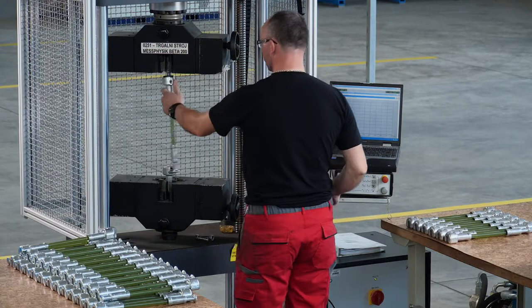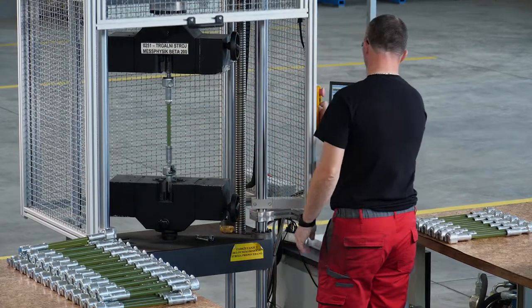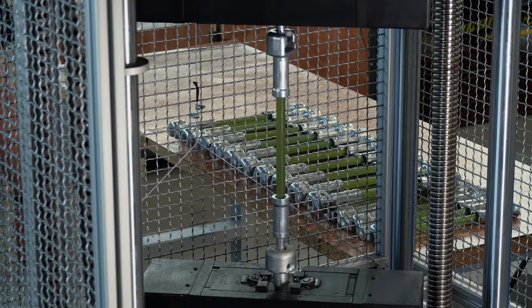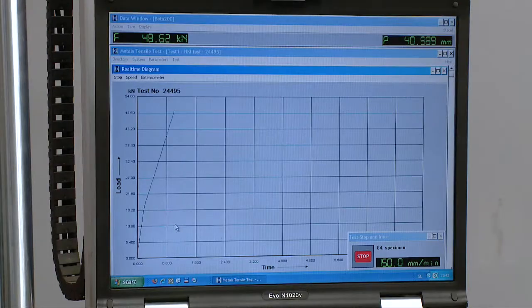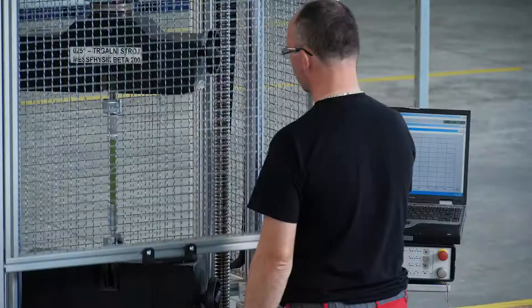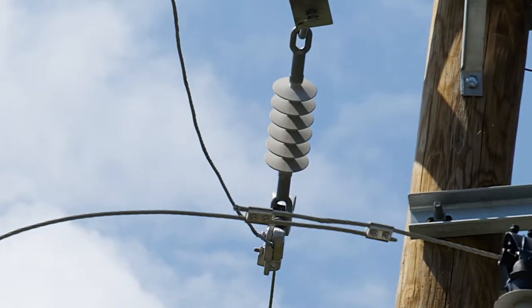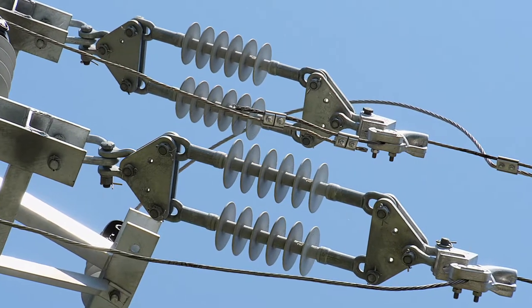In accordance with the standards, we also perform a tensile test on each insulator using a universal testing machine before siliconizing to ensure the fittings are adequately pressed onto the epoxy rod. Depending on the fitting type, the mechanical destructive force is 90 kilonewtons.